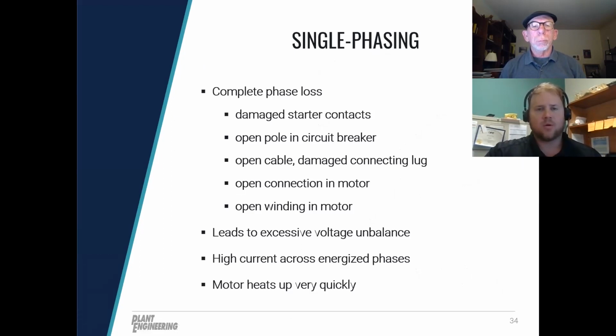So the fourth power quality issue we talk about is single phasing. Single phasing is the most severe form of voltage imbalance. They kind of go hand in hand. Single phasing can be caused by many different things: a damaged starter, a damaged circuit breaker, broken terminals at the motor, bad connections, bad wiring, maybe even, in a severe case, downed power lines.